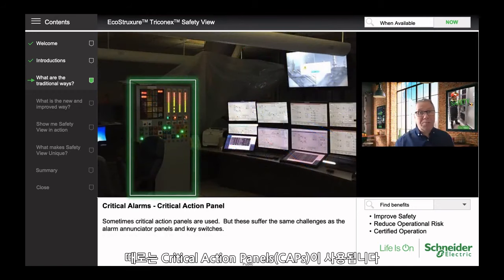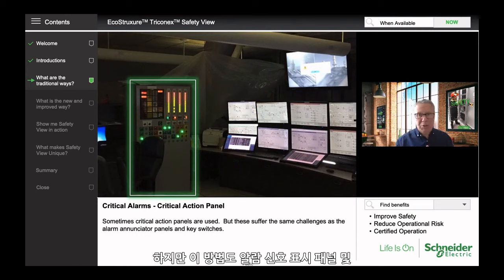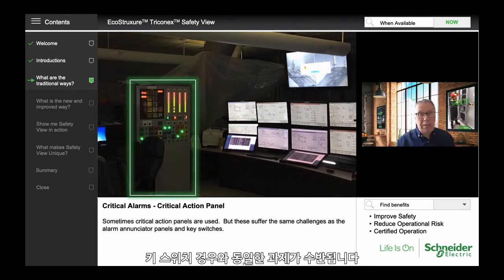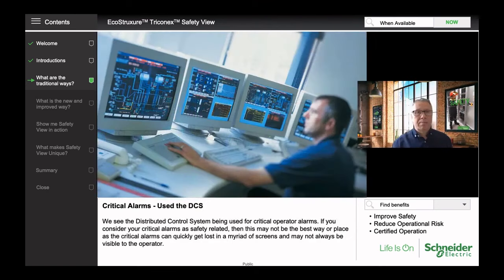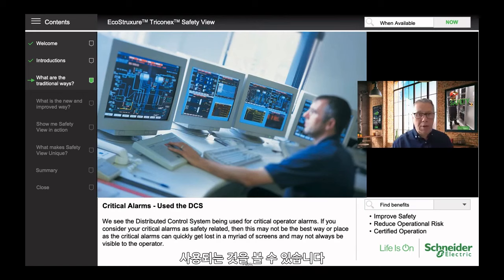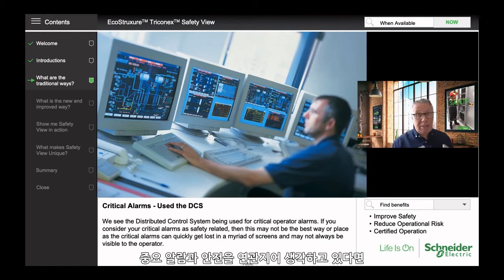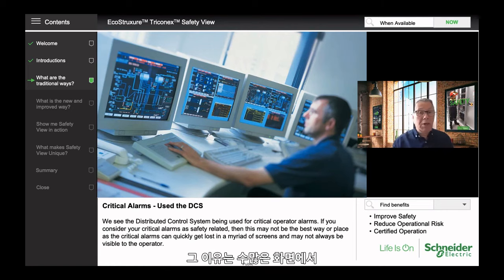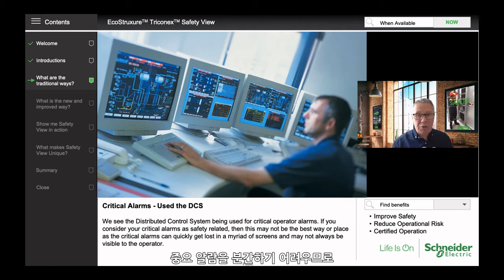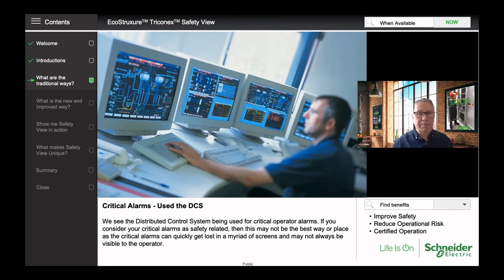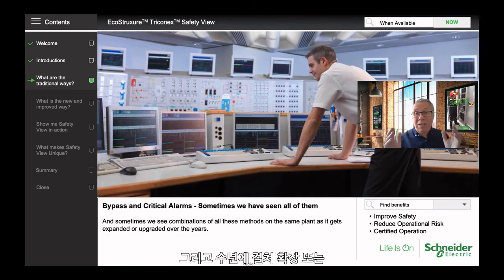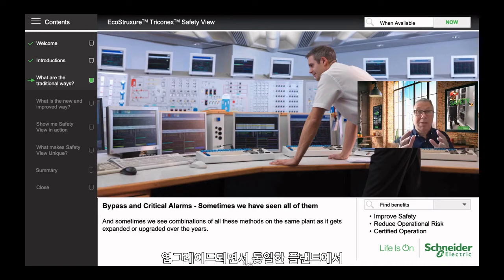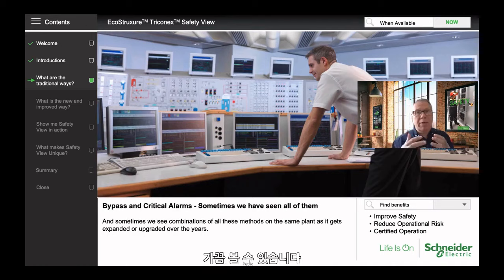Sometimes critical action panels are used, but these suffer from the same challenges as hardwired alarm enunciator panels and keyswitches. We also see the distributed control system used for critical operator alarms, but if you consider your critical alarms as safety-related, this may not be the best place — as critical alarms can quickly get lost in a myriad of screens and therefore may not always be visible to the operator. Sometimes we see all combinations of these methods on the same plant, especially as it gets expanded or upgraded over the years.